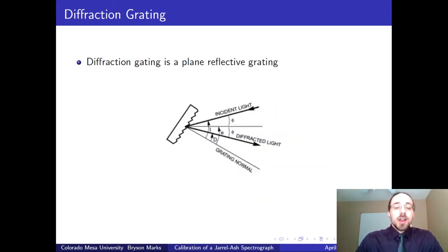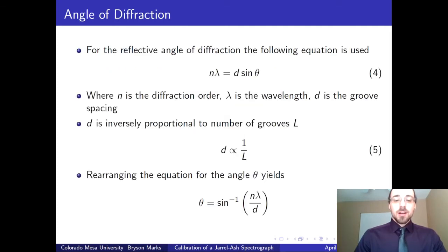Now, the diffraction grating that is being used is a plane reflective diffraction grating, where we have an incident of light coming in, reflecting off the grating and diffracting, as in this cartoon here.